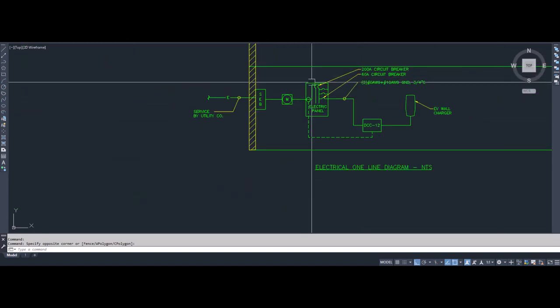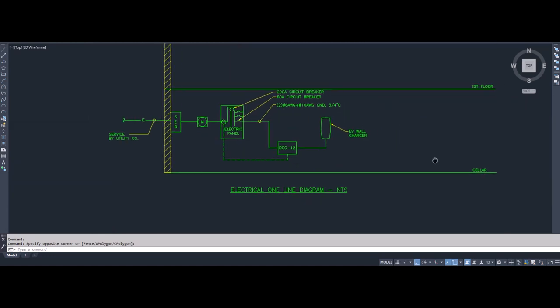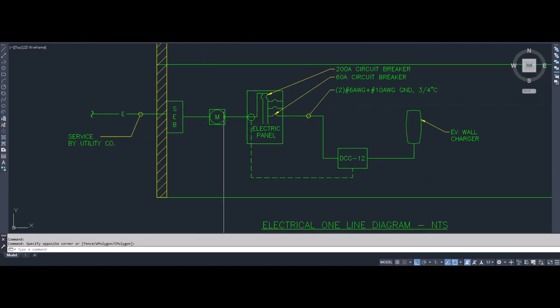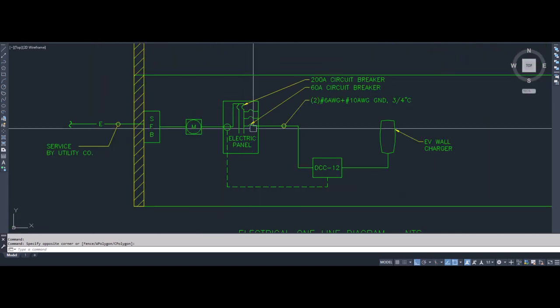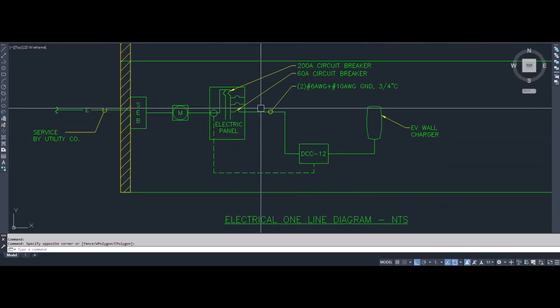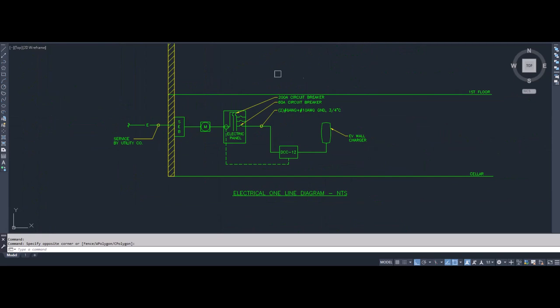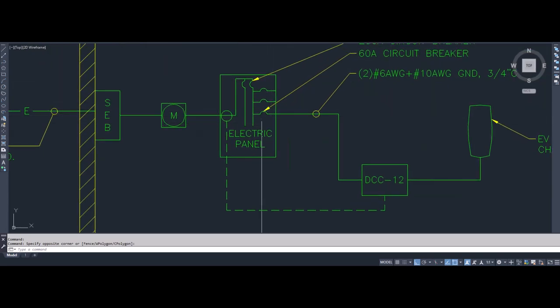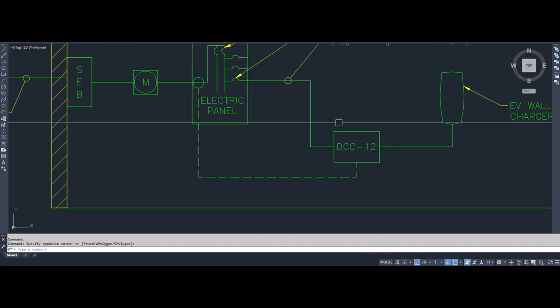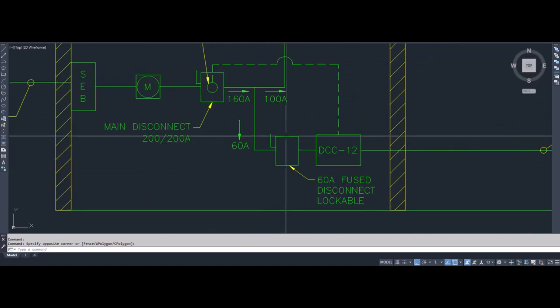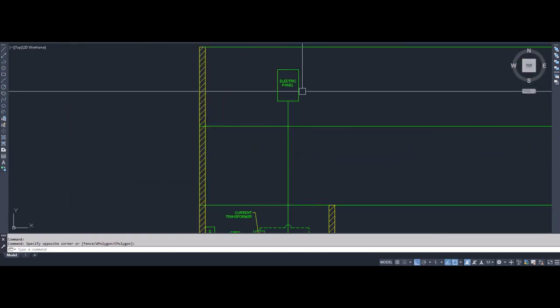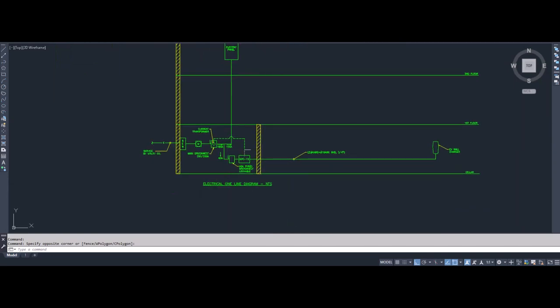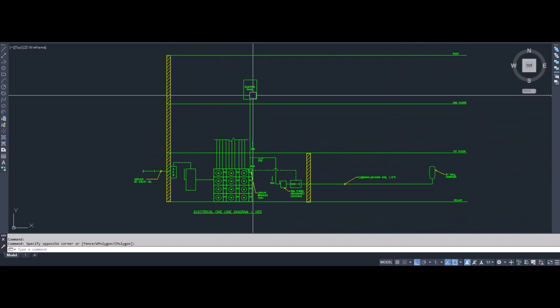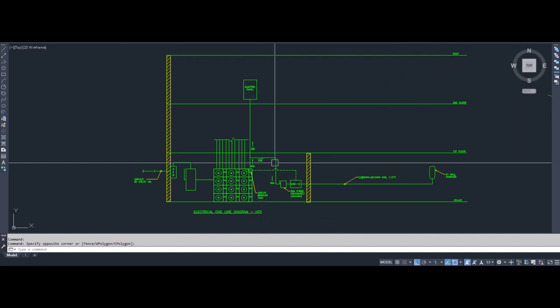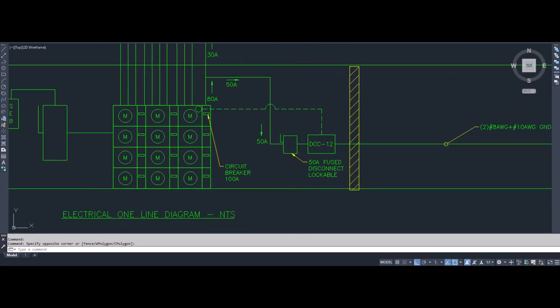So let's start with this one here, where the service comes in underground in the cellar, and you have a meter, and then you have your main disconnect in the panel itself, and then it goes out to your loads wherever they may be. And in this one, since everything is very close together, you can use the breaker in the panel to feed your DCC12 rather than installing a separate disconnect.